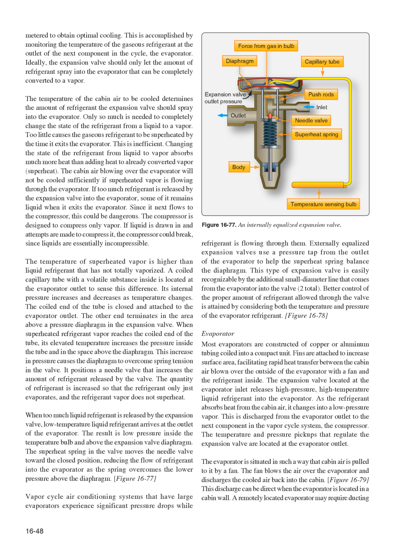Figure 16-77, vapor cycle air conditioning systems that have large evaporators experience significant pressure drops while refrigerant is flowing through them. Externally equalized expansion valves use a pressure tap from the outlet of the evaporator to help the superheat spring balance the diaphragm. This type of expansion valve is easily recognizable by the additional small diameter line that comes from the evaporator into the valve, two total. Better control of the proper amount of refrigerant allowed through the valve is attained by considering both the temperature and pressure of the evaporator refrigerant.